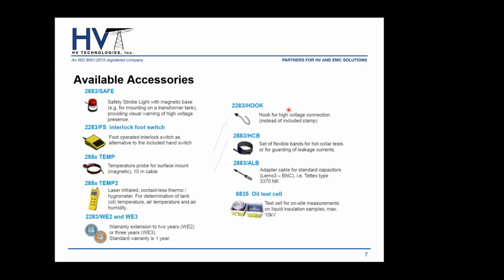Instead of a clamp, on your high voltage cable, you can also screw in a hook. That sometimes is convenient. You will also get a set of hot flexible bands for your hot collar test or for your guarding circuits. And then if you need adapter cables for standard capacitors, if that's necessary, so you can switch from LEMO 3 to BNC. And also, for those who are interested in liquid or oil test cells, it can also be provided with a test cell for on-site measurement of transformer oil, for example, up to 10 kV. So with this, you have basically a complete setup for dissipation factor and capacitance measurements of basically any device.